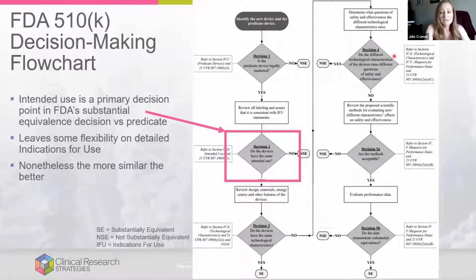So if they do not, if we're good to go, there's no new questions of safety and effectiveness, then we're going to review the proposed scientific methods for evaluating those different characteristics. You're going to need to provide some kind of evidence that even though you have different technical characteristics, it doesn't raise new questions. So that's what you're going to need to do next. Are the methods acceptable of how you have made that comparison? If they are, then you evaluate the performance data. And you move on to the last question, does the data demonstrate substantial equivalence? If it does, then you're good to go. The FDA, you've made it this far, they're going to say you're substantially equivalent. They'll then clear your 510K as long as you've met all these requirements for your predicate device.